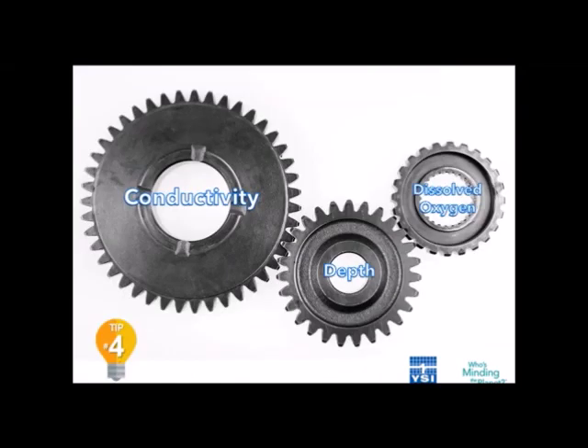Now, because a conductivity sensor is typically the only sensor that's left unprotected from biofouling, as Tiffany had mentioned, there are wipers, but the wipers really only reach the other sensors, not conductivity in general. It ends up driving the maintenance interval for that reason alone. So left unchecked, if you have fouling on a conductivity probe, that's not only going to impact the conductivity parameter you see in your data, but it also will affect dissolved oxygen and depth or level parameters as well, because those use conductivity readings to compensate for changes in salinity.